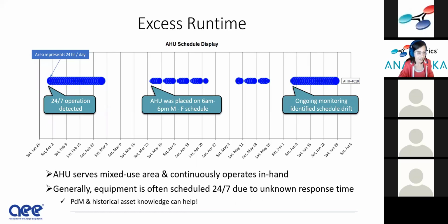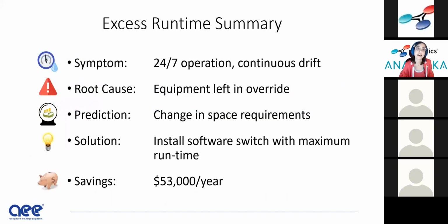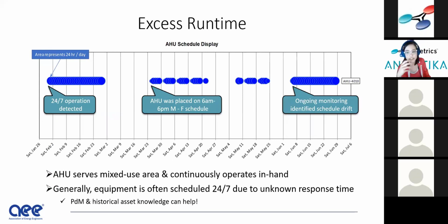And we actually have. We said, does this need to run 24/7? Maybe it can be placed on a schedule, or maybe it was on a schedule and we're finding it can't be anymore. A lot of times equipment is left in 24/7 operation because of an unknown in response time. I found that people don't know how long it is going to take for my space to get up to temperature. I don't want to have some unoccupied set point and let it drift, and now I'm getting hot and cold calls in the morning. I'm just going to let it run 24/7. That was the case with this unit. There was steam piping in the ceiling. They were really nervous. Even though it was insulated, it was getting really warm in a room.